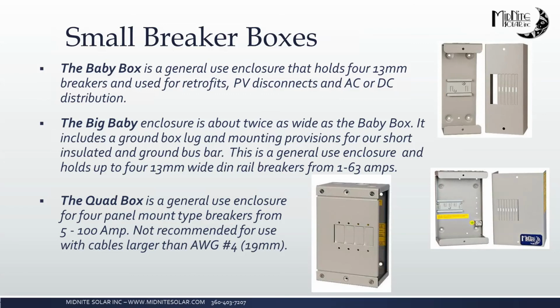It's about twice as wide as the baby box, and it does include the ground box lug. It also gives you a little bit more space for wiring, which can be a little bit more convenient so that you don't smack your knuckles on things. It's a great general use enclosure, and it holds 4 of the 13 millimeter wide DIN rail breakers, which range from 1 to 63 amps. We also offer the quad box in case you need a panel mount breaker box. It holds 4 of the panel mount style breakers. Those are available from 5 to 100 amps. And we do not recommend using larger than 4 AWG in this. It gets pretty tight in there, so that's about the largest you'd want to use.